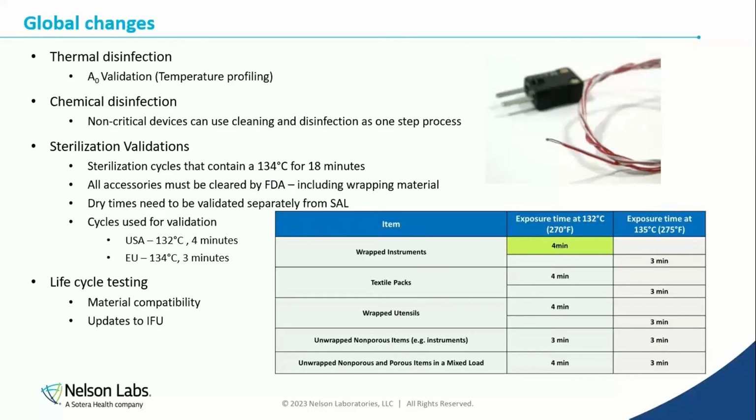And chemical disinfection for non-critical devices. Before, what we did is we did cleaning validations and we did disinfection validations, right? Separate validations. And so we have a longer contact time.